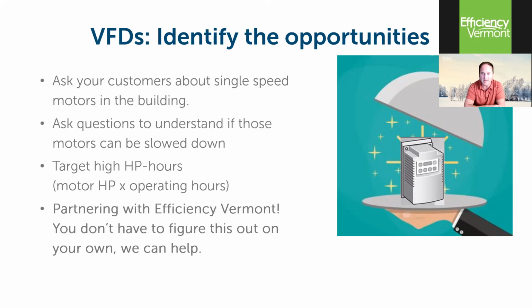And if it's a really complicated or one application that is in question, we may just submeter. We'll put a power logger on the existing motor and we'll get a profile on it for 2 weeks. And then we'll map out what we think we can look at in terms of turn down with the drive, and that'll forecast the energy savings. We marry that up with the cost of the project and the rebate, and we get a payback scenario for the owner. And in many cases, it's nothing but green lights on these. So next slide, please.